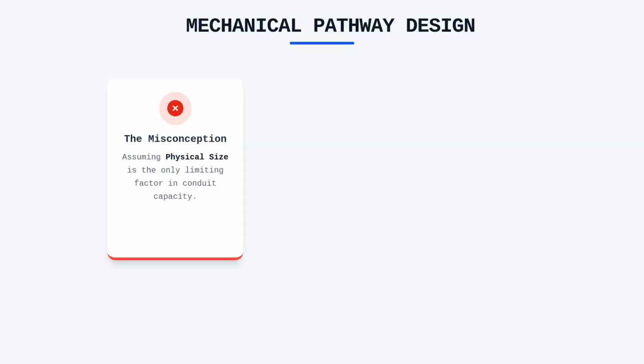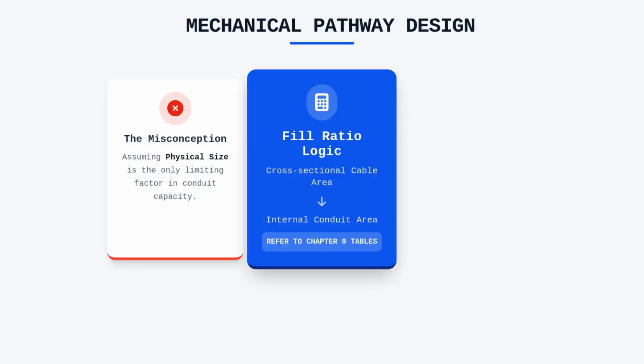Finally, we must address the mechanical aspects of pathway design, specifically conduit fill capacities found in Chapter 9. Many designers make the mistake of assuming that the physical size of the conduit is the only limiting factor. Instead, the code relies on percentage fill tables that account for the cross-sectional area of the cables relative to the internal area of the conduit.